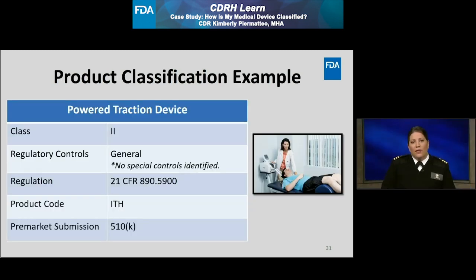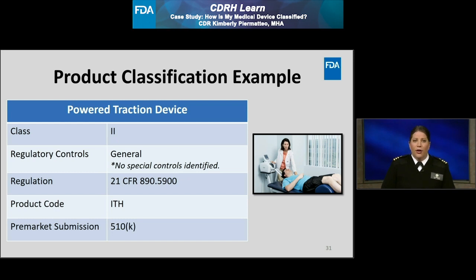To conclude this case study example, the table provided on this slide summarizes the results of the various searches I conducted using methods 1, 2, and 3. By using all three methods, I was able to come to the same conclusion regarding the appropriate product classification for my powered traction device. I can conclude that the appropriate class for a powered traction device intended to treat low back pain through intermittent and static traction is class 2 and must comply with general controls. The appropriate regulation number is 21 CFR 890.5900, the product code is ITH, and a 510K clearance is required prior to marketing this device.